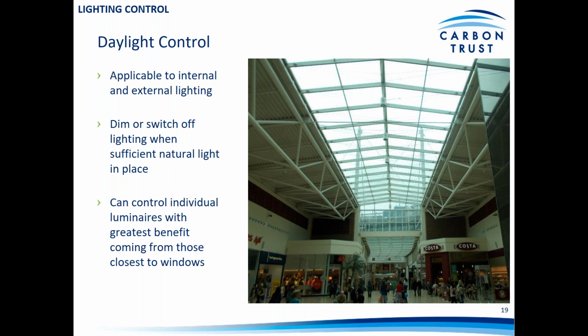If that changes, if it gets dark at night, or if it clouds over particularly, then the lighting can come on, and it can either ramp up or switch on to full brightness. And using daylight control coupled with LED technology is very effective due to its dimming capabilities and its ability to adjust its brightness over a wide range.